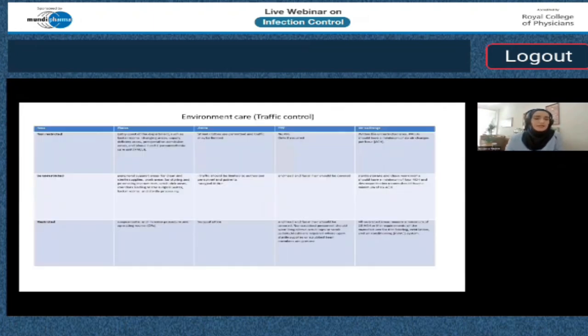Now, we mainly have 3 zones in the operating room. First is the non-restricted area, which is the entry points to the department, such as the locker rooms, changing areas, supply delivery area, preoperative admission areas, and phase 1 and phase 2 post-anesthesia care unit. In this area, surgical attire is not required; even street clothes are permitted. PPE is not indicated, only if it is required, for example if there is any kind of infection. Within this unrestricted area and PACU, there should be around 6 air exchanges per hour.